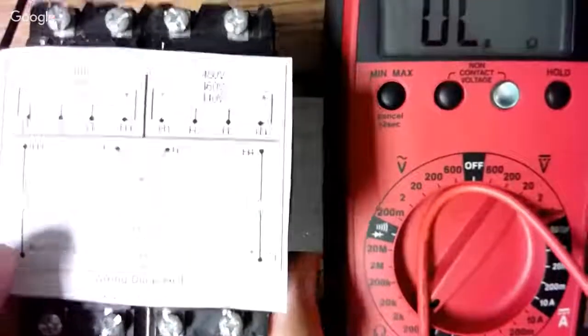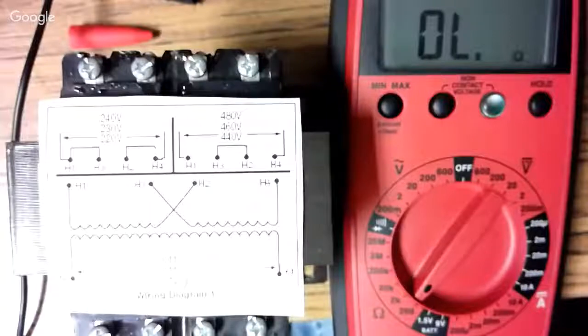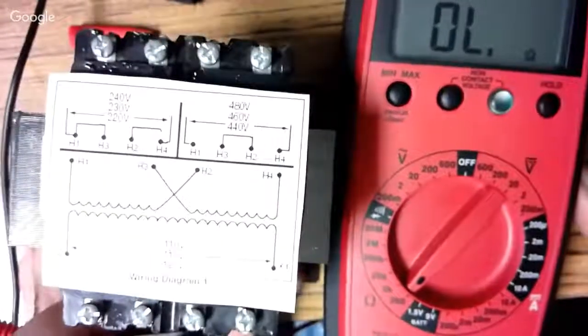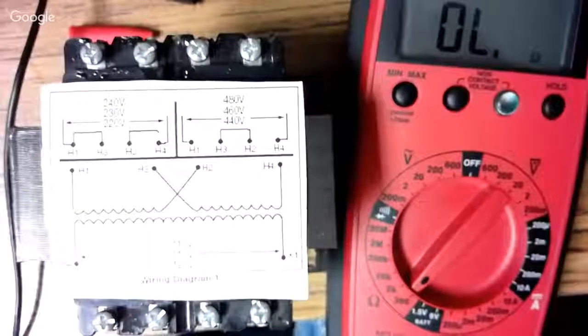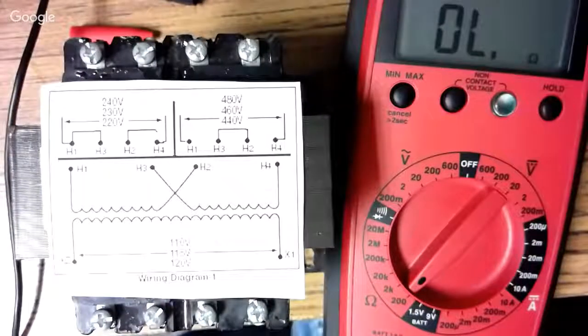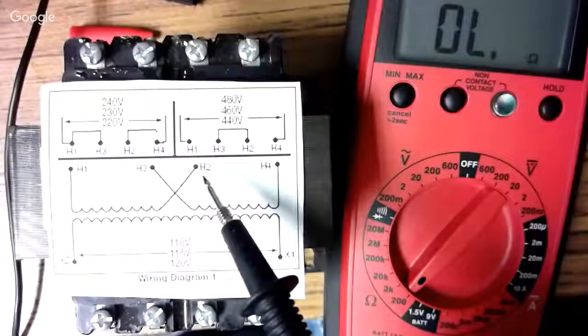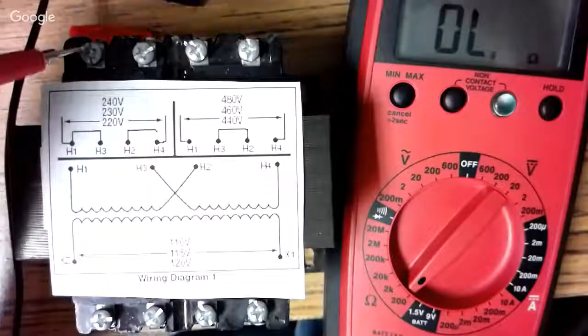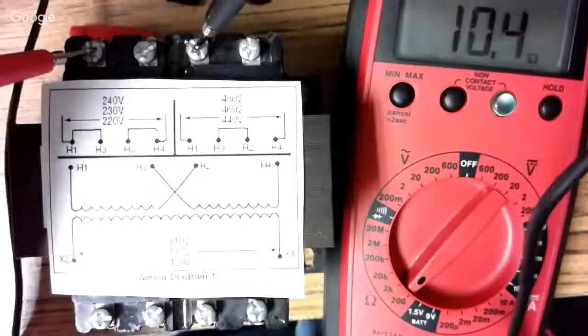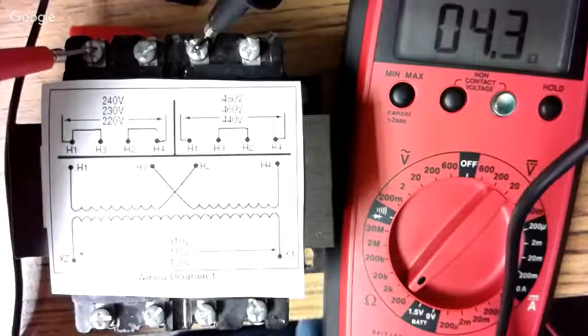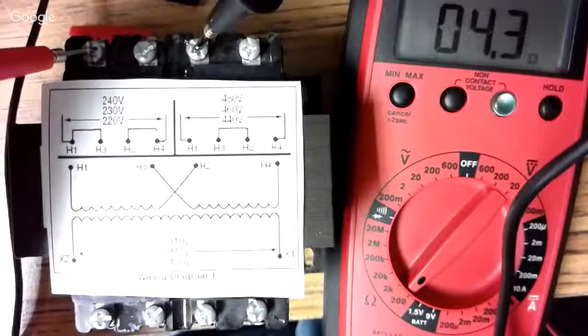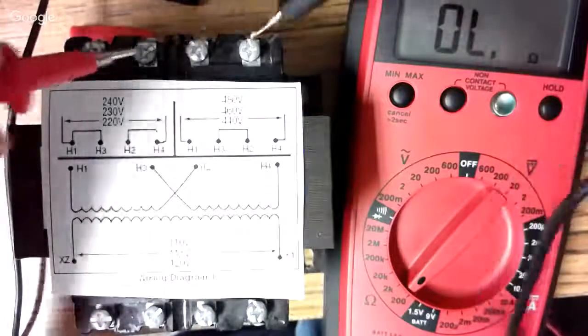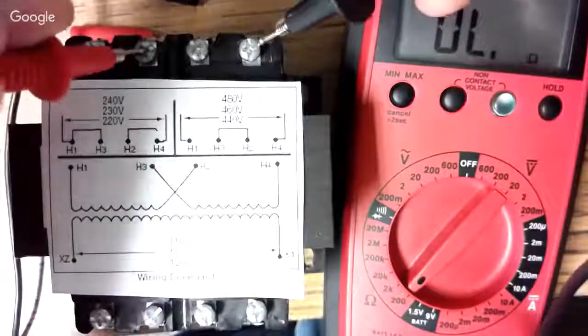See if we can get a little better view here. So we're going to be checking H1 to H2. This is one coil. I'm going to hold my meter steady until it stabilizes. Notice it's fluctuating quite a bit. Eventually it comes to rest around 4.2 to 4.3 ohms for one side of the coil. So now I'm going to check the other side, which is 2 over. We're checking H3 to H4.